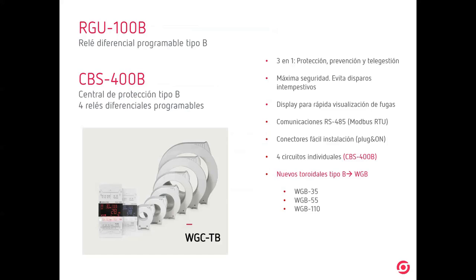And type B is exactly the same situation, but for DC loads or DC plus AC, when we have loads like variable speed drives, climate stations, UPS, electric vehicle recharging, etc. We are consuming AC and DC. You have an internal DC bus, and this bus can leak. So you have a leakage with a DC component. The type A relays will not be able to trip correctly. Later on we will see the effects, but they will not work correctly. If you want to ensure correct tripping for saving people and saving installation, you must go to type B.